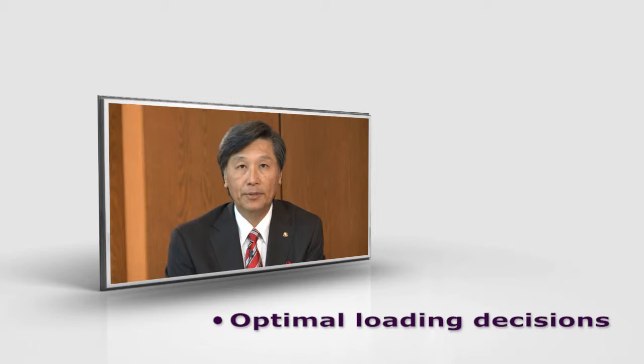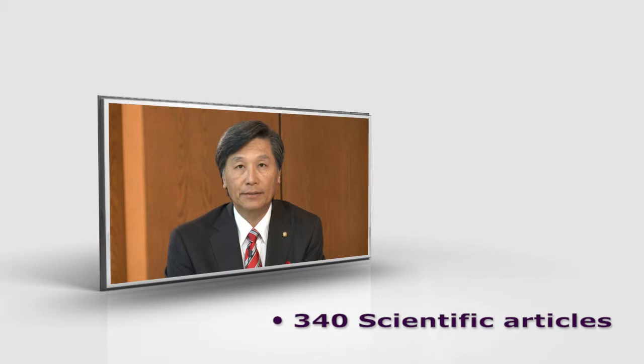Osstell makes it possible not only to measure the initial implant stability, but also to monitor the progression of osseointegration over time and helps me to decide optimum loading periods. It is a scientifically proven method with more than 300 published articles in scientific journals supporting the core technology and the use of ISQ measurements.